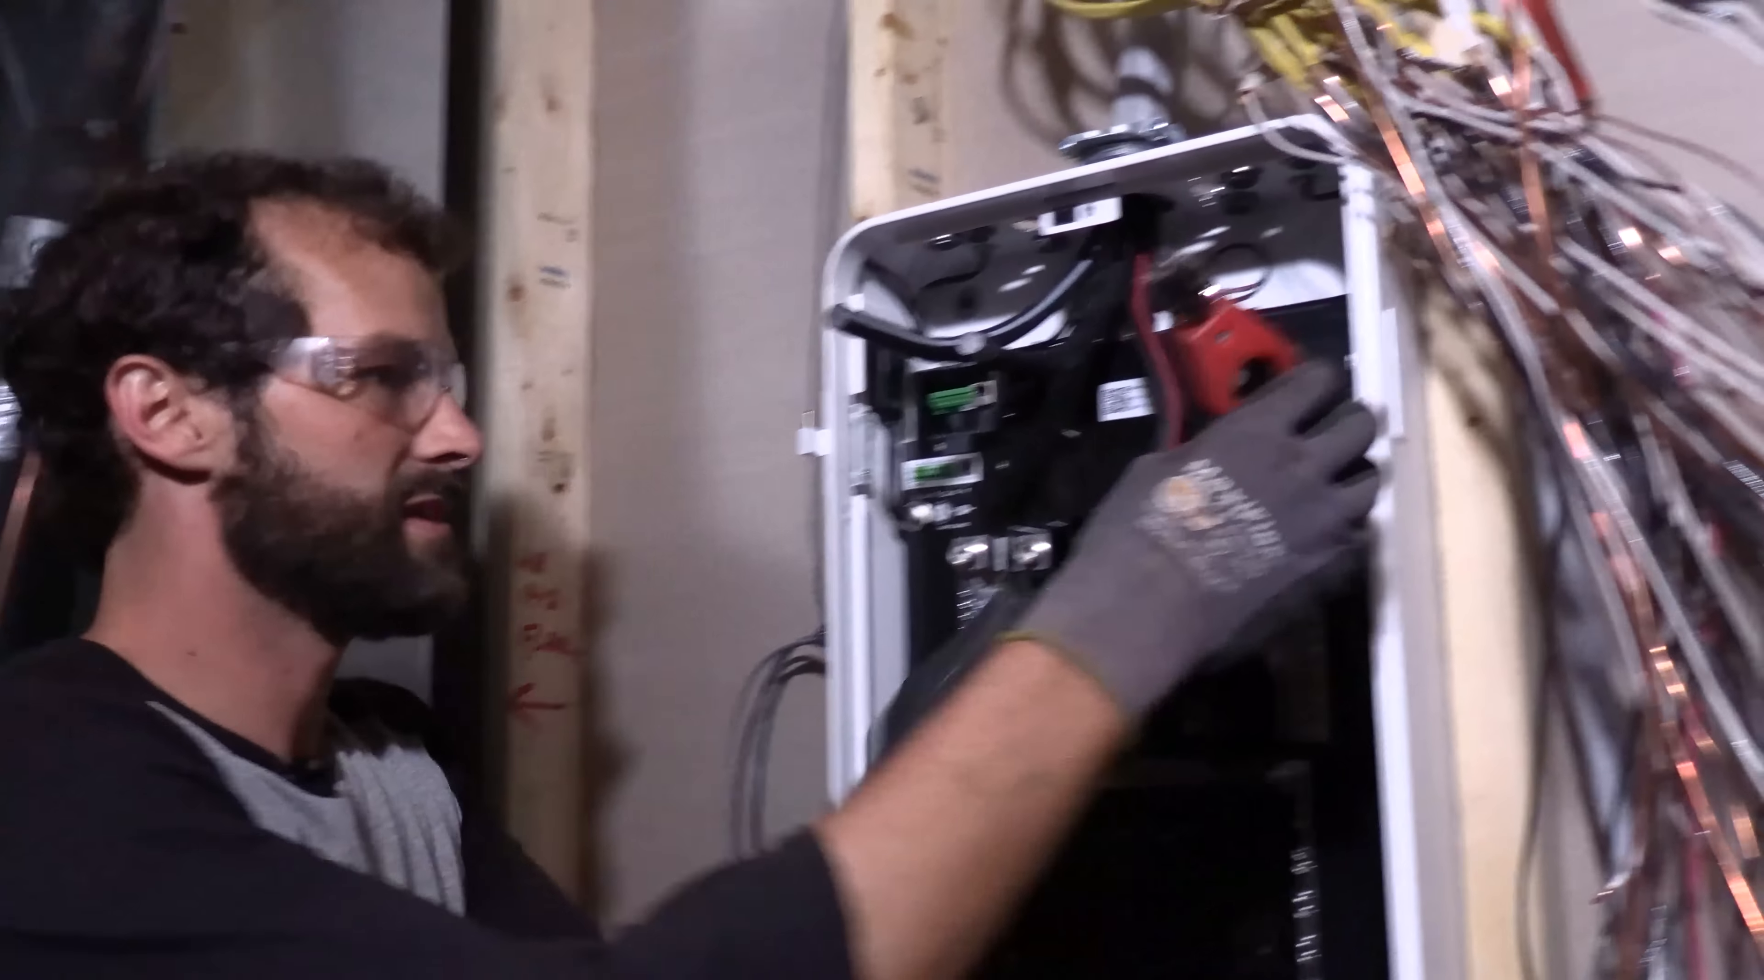We've got to No-Alox these babies up. Anti-oxidation compound. The inspectors will fail. It's not going to hurt anything, even on aluminum alloy, and the inspectors are going to fail it if they don't see an ample amount of anti-oxidation compound. And then this brush actually comes from the plumbing department, but man, it's so quick, cheap and efficient. Get a good wire brush on there.